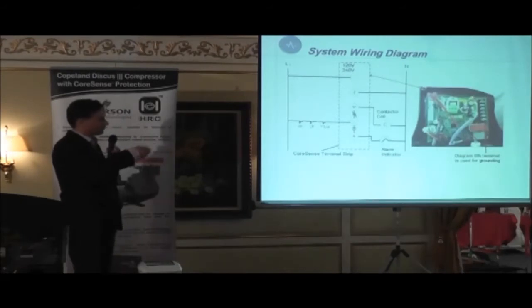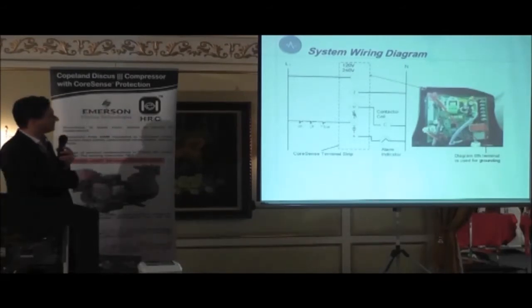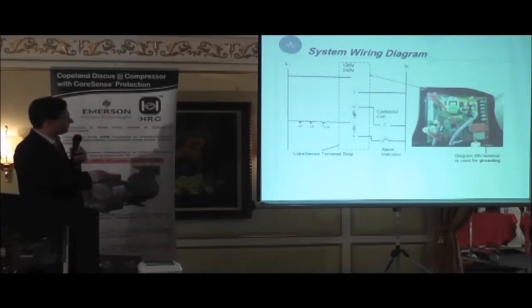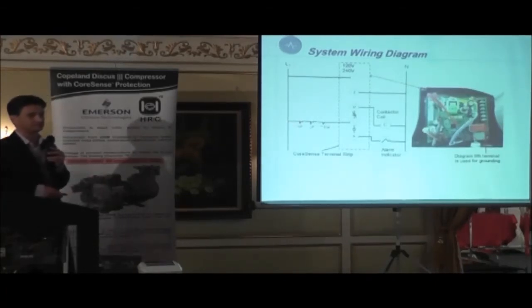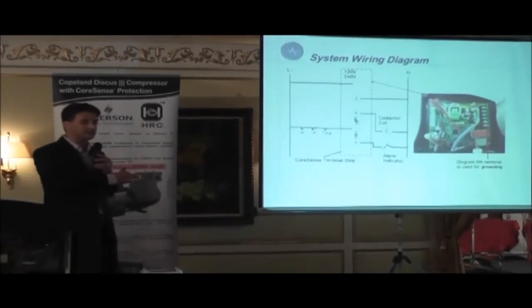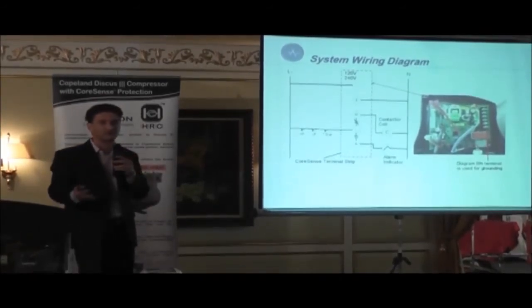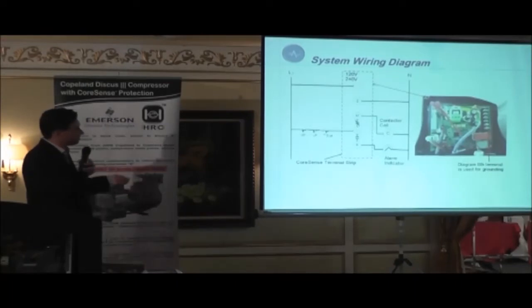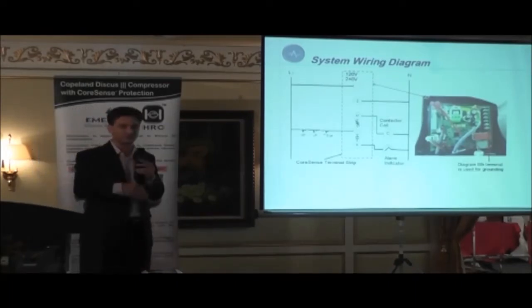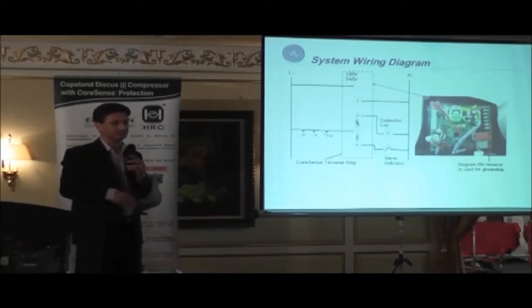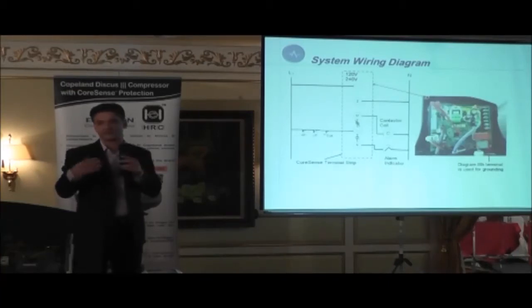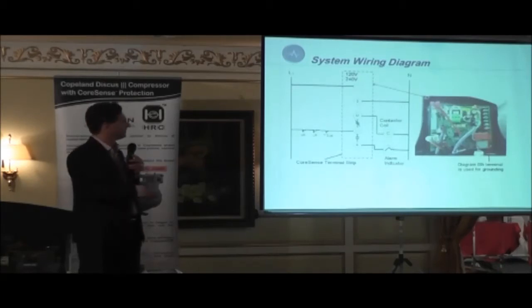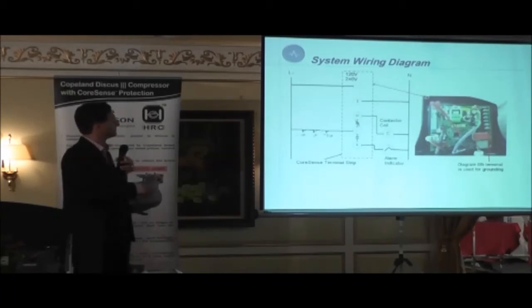So this is the wiring schematic. It's very simple. Power supply, and then your control circuit. Right. Now this wiring is a lot simpler than what we were offering before, because this module now includes the thermistor module and the oil pressure switch. So it will reduce the amount of wiring you need to do as accessories that were fitted to the compressor. Here we just have a 5-wire connection. Okay? So this is just a 5-core.